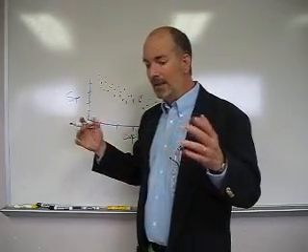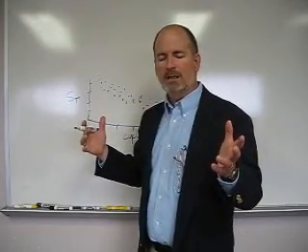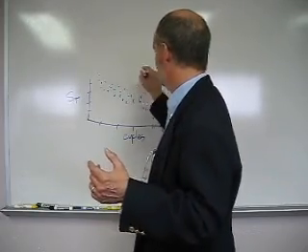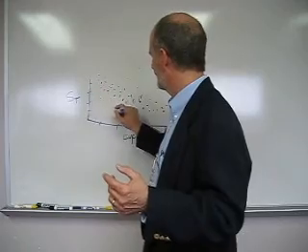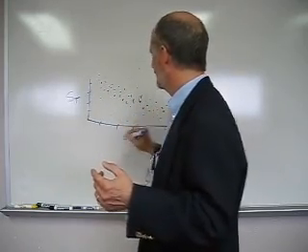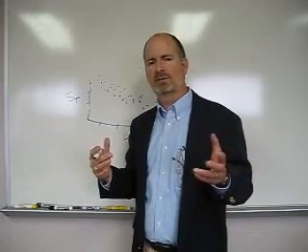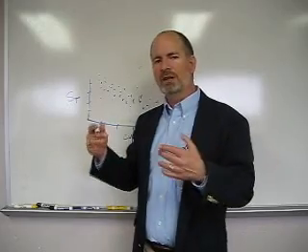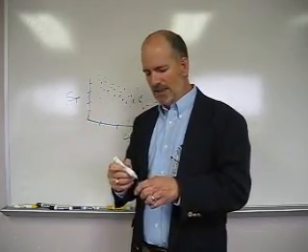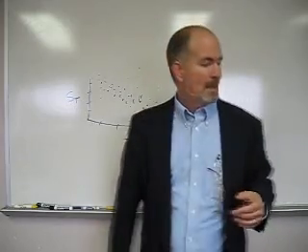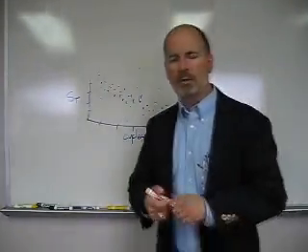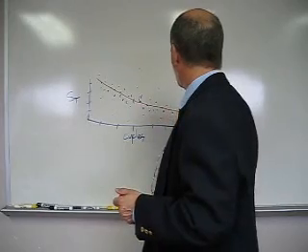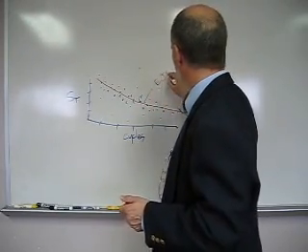And you would expect from lots of different manufacturers, most of the methods are all the same, but you had some really good scatter points up here, and you had some flyers down here. Any time you develop a curve like this, and the more data points you get, you're going to get some scatter on the high ends and low ends. And EJMA took all these blue dot data points and they did a best fit curve, which goes right through the average of all of them, and that is the EJMA fatigue curve.